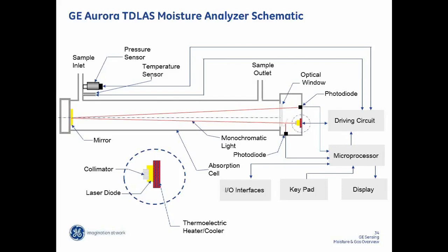The laser is actually scanned 3 times a second. We take 3 measurements every second. And the base of the laser is precisely temperature controlled. There are 2 ways to change the frequency: change the temperature of the laser or inject current into it. So we're ramping the laser by injecting current into the laser diode, and that essentially changes its frequency.